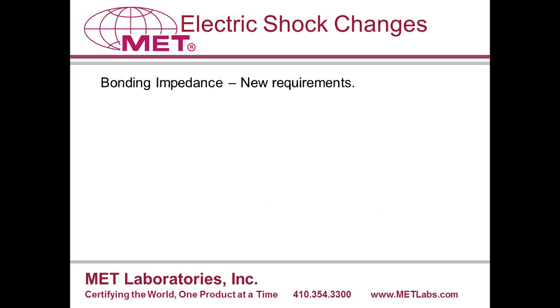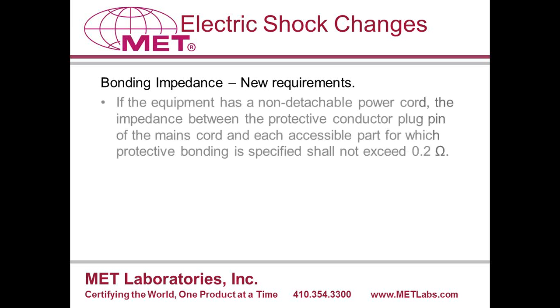Next, there are some changes to the bonding impedance test. The first change is that the new limit for non-detachable cords, instead of 100 milliohms, is now 200 milliohms. Again, this is for non-detachable cords. And it's tested from the end of the cord to any point on the enclosure which is accessible.